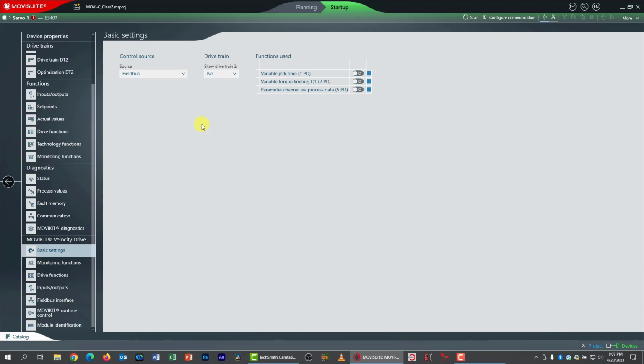Now, this is something we have to do because we're in an open loop control mode. If we had an encoder, a closed loop control mode, we wouldn't need to do this step, but in open loop mode, the system doesn't know the motor's exact speed because it has no direct feedback. It sort of estimates it by measuring motor current, and it also knows, of course, how it's pulsing, the pulse width modulation. But we need to activate a safety feature here that we use in open loop modes, and we're going to use this since we're in ELSM mode. If you were in VF mode, you should also use this. That, of course, would be with an asynchronous motor.